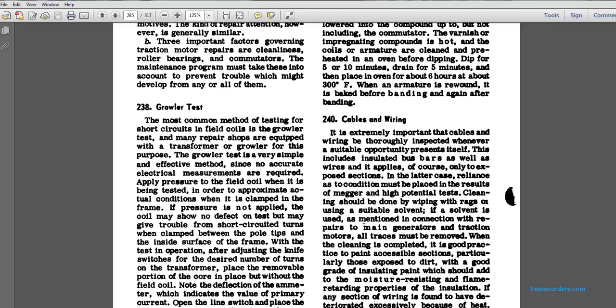240. Cables and wires. It is extremely important for the cables and wiring to be thoroughly inspected whenever a suitable opportunity presents itself. This includes insulated bus bars as well as wires and splices, of course, not only exposed sections. In the latter cases, the resulting condition must be placed in a megger or high potential test. Cleaning should be done by wiping with rags and using a suitable solvent.